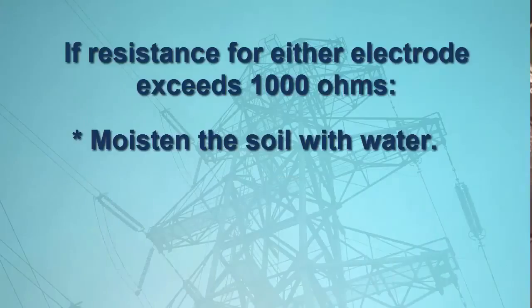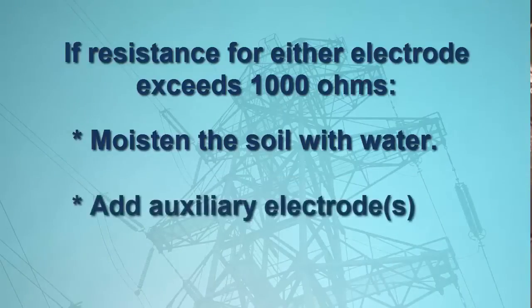You can also connect additional auxiliary electrodes to each test electrode. These auxiliary electrodes should be placed in parallel with the primary electrodes at a distance of approximately 2 to 4 times the depth of the primary electrodes.